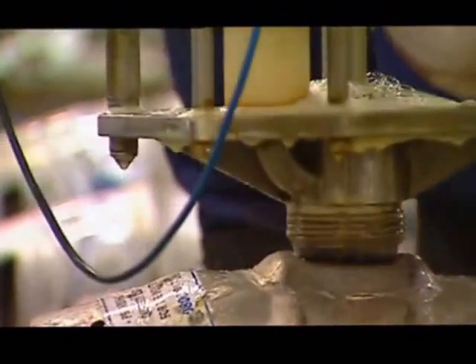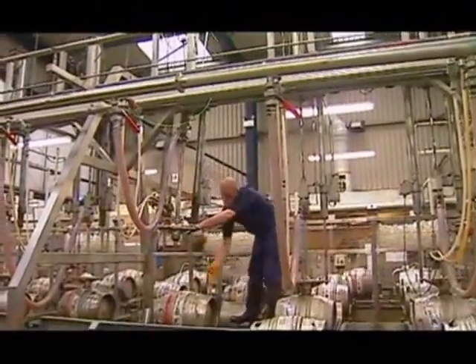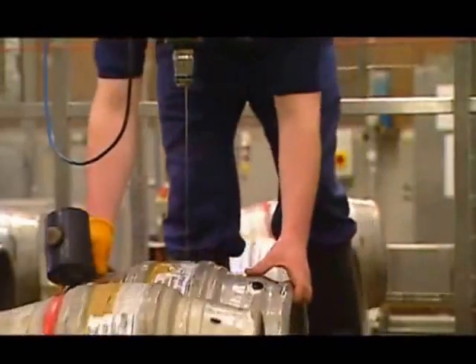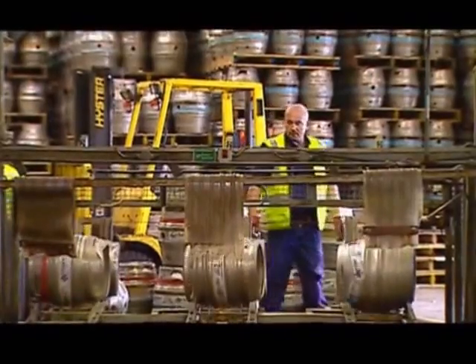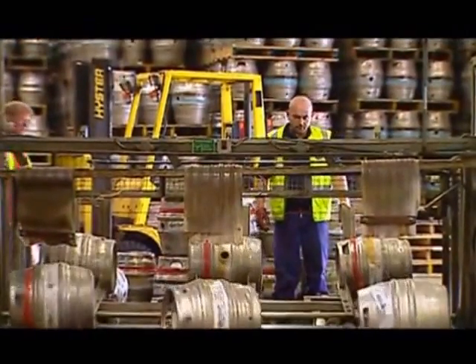We used to go around and service the traps on a twice-a-year basis — lots of spare parts, lots of man-hours. Now there's basically no maintenance whatsoever, to the extent that you've got no engineers running around doing trap repairs. Gem traps look after themselves.